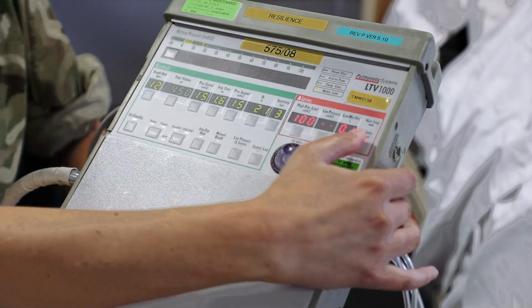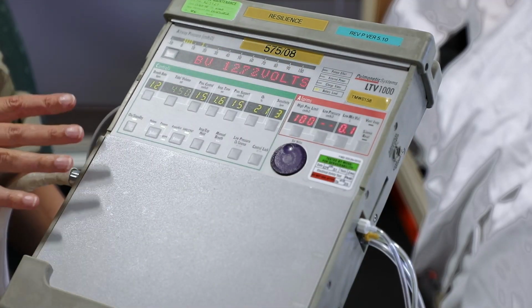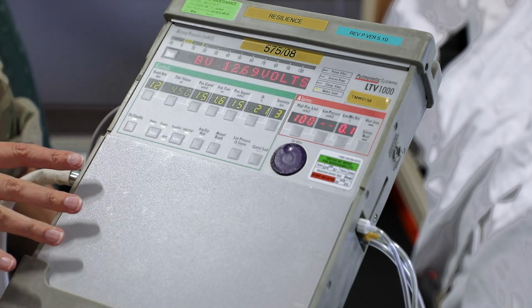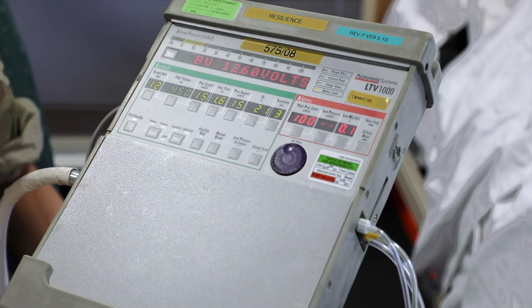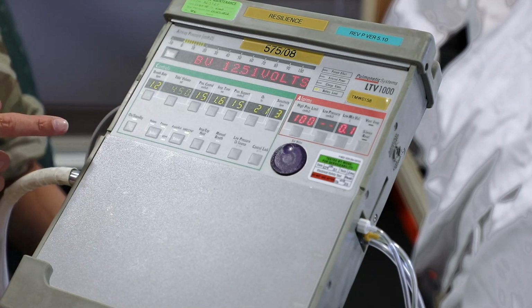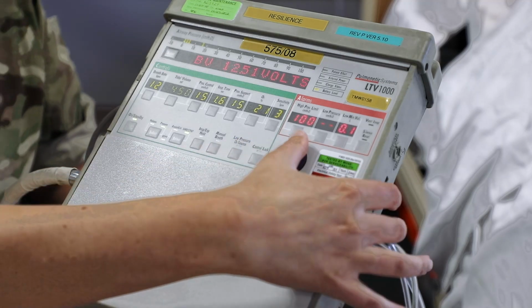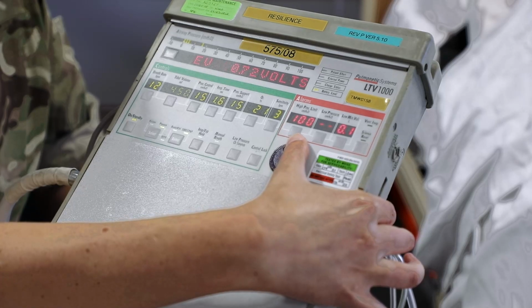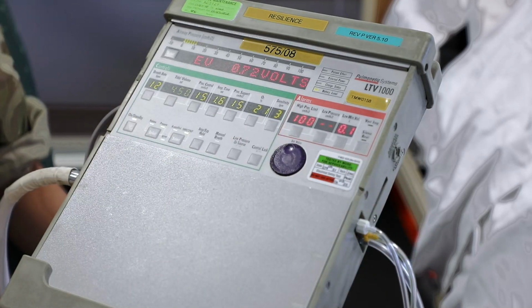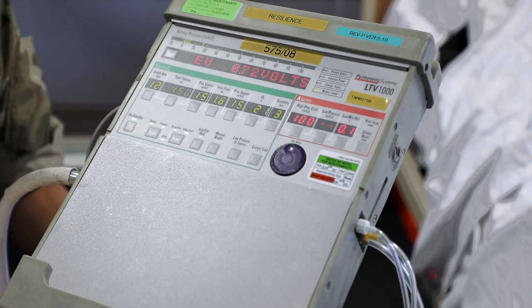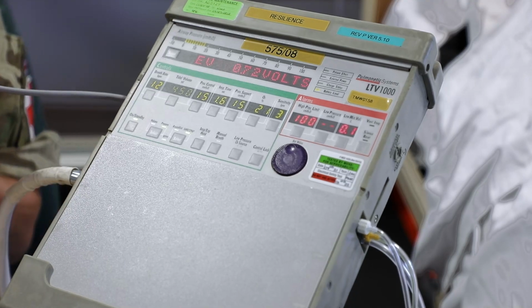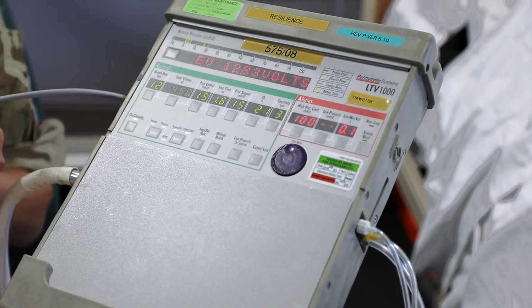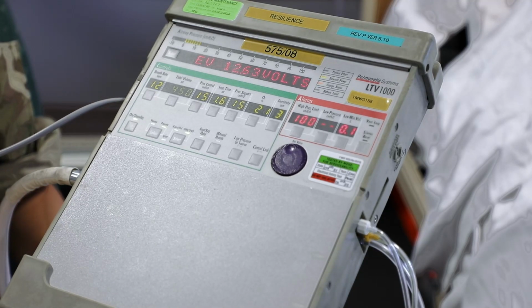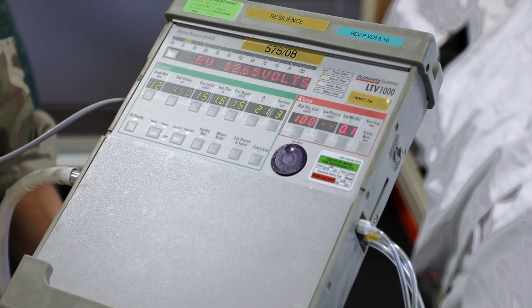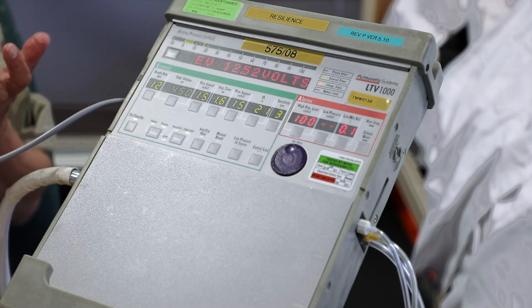Just silence that alarm and reset it. This is calculating the voltage of the internal battery, and we need it to be greater than 12 volts, which it is, so that's suitable. This is also where we would check any external batteries. To confirm our external voltage, if we scroll to the right, we now have an option for external voltage. To do that, just connect up your battery in the same way as you'd connect up the main supply. And again, look for a voltage of greater than 12, which is sufficient and means that your battery should last for the expected 3 hours.